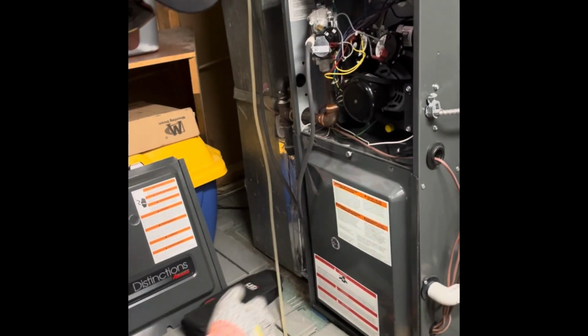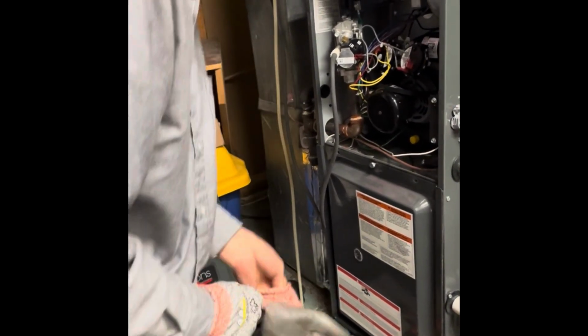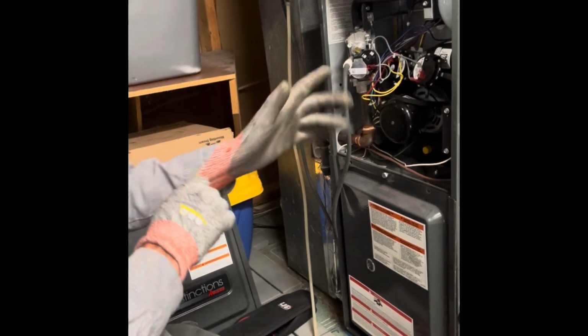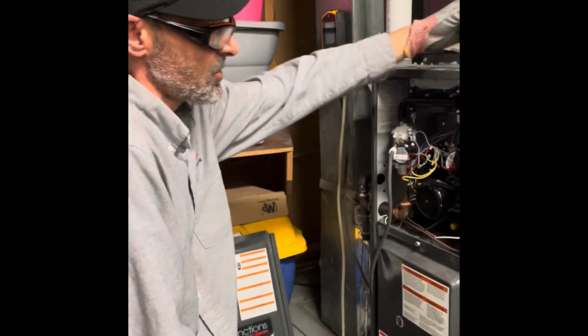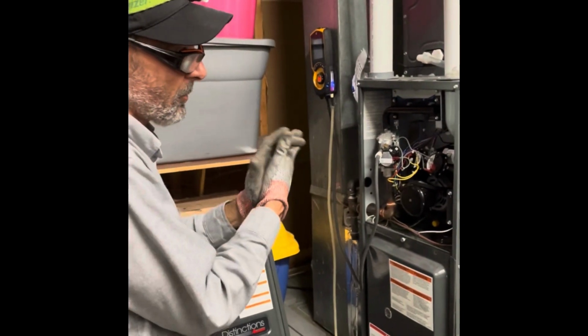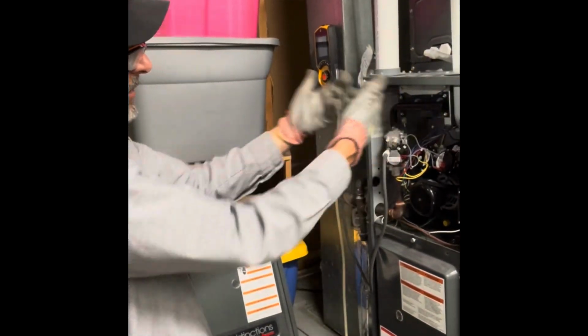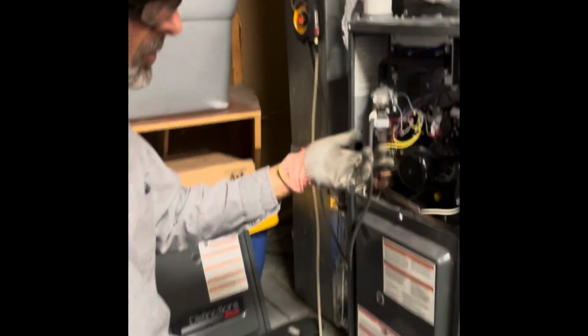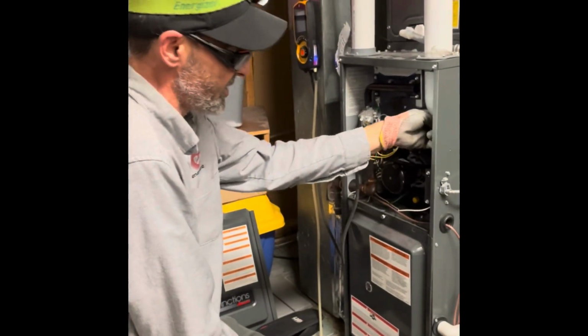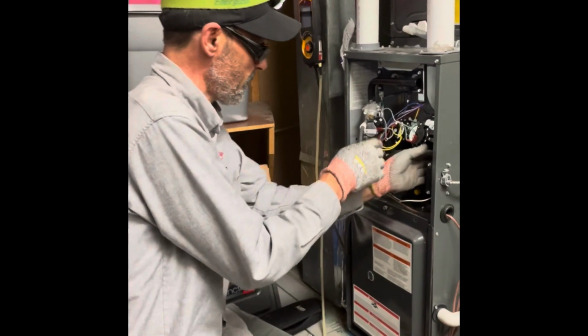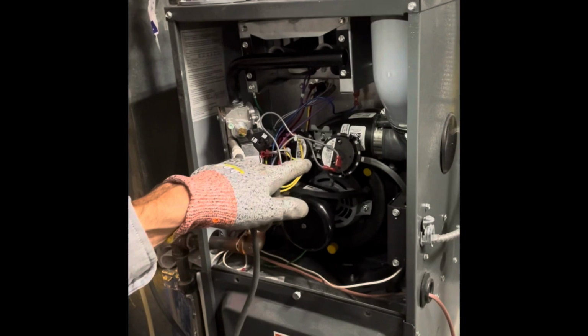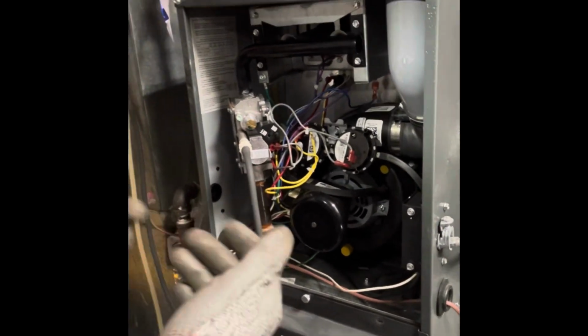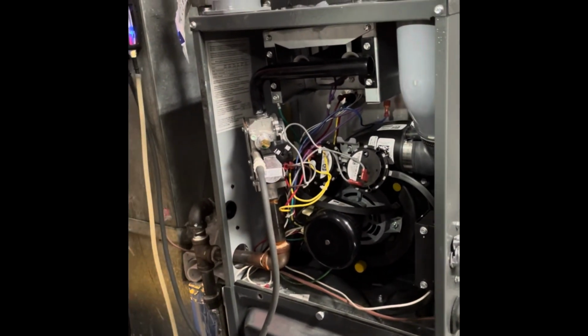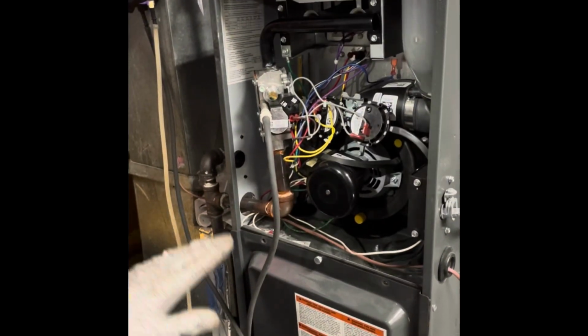Just before I do that, I want to test out the pressure switch safety. This safety is incorporated with the venting system, so that if a bird flies in the vent or if snow plugs up against it, they don't want these fumes coming back in the house, because there are products of combustion, being carbon monoxide, in there. So I'm going to pinch this hose. Burner's turned off. That confirms our pressure switch is operating properly. I duplicated that vent being plugged, so once it gets plugged, I want the switch opening, killing the power to the furnace. So we're going to give it a minute.